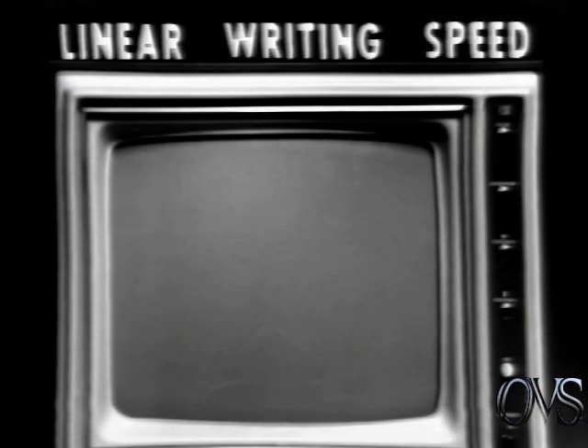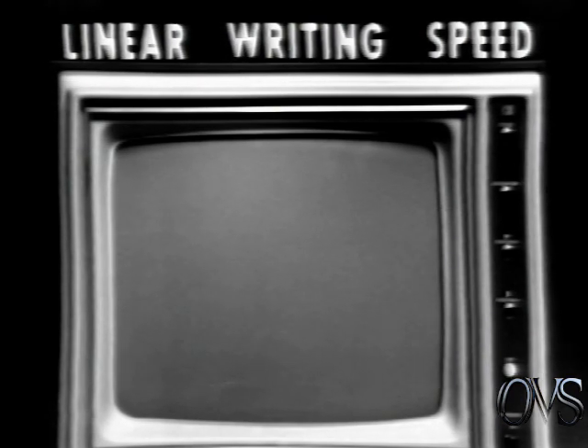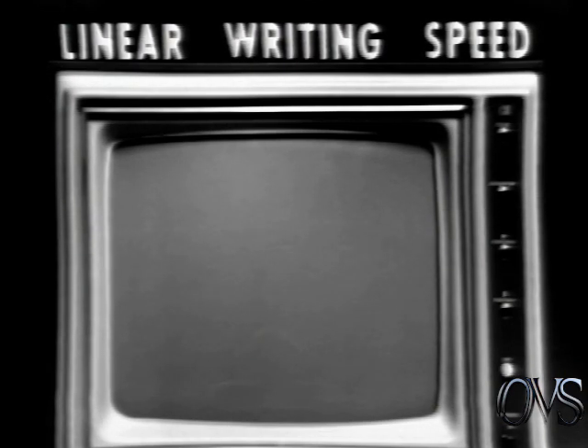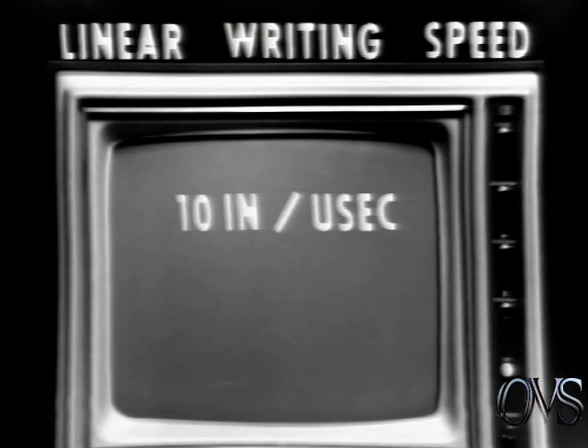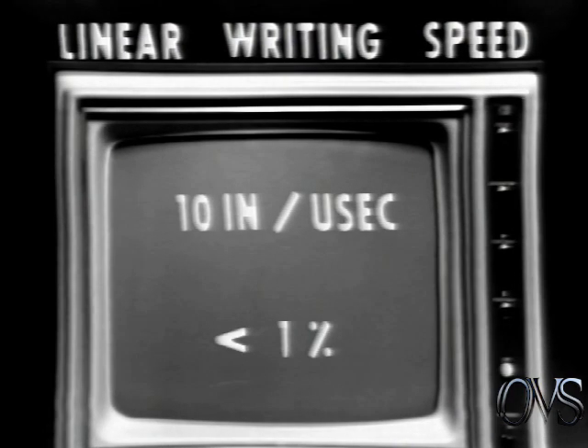Next, we'll discuss several specifications that are unique to large screen display devices. First, linear writing speed. This is specified at greater than 10 inches per microsecond on both instruments. This means that the beam can be deflected in any direction at a speed of 10 inches per microsecond with less than 1% of nonlinearity. Both instruments will write faster than this, but with degraded linearity.